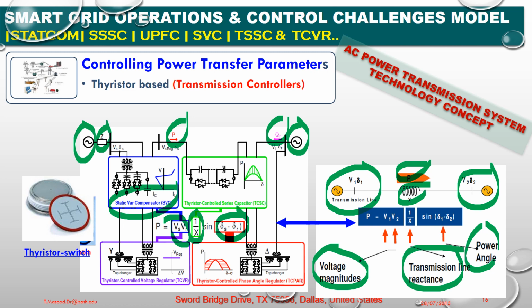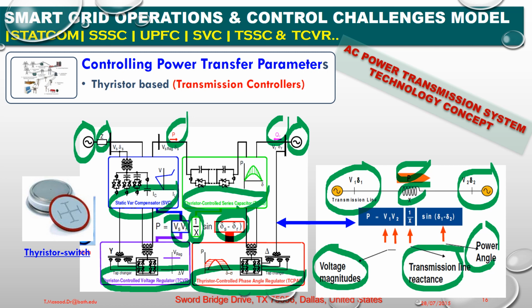To improve voltage, I use a thyristor controlled voltage regulator, TCVR. In the center, I use a thyristor controlled series capacitor, TCSC, to control line impedance. The third device, and the fourth power electronics based device, is the thyristor controlled phase angle regulator, TCPAR. These four power electronics based devices are used to deliver seamless operation and maximize power delivery in the transmission network.